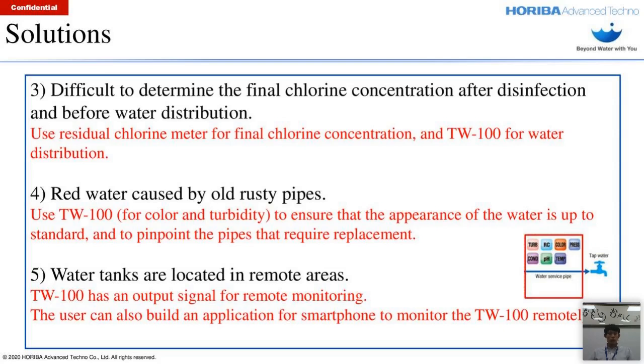For challenge number four, red water caused by old rusty pipes. The solution for this challenge is to use the TW100 series again to monitor the color and turbidity of the water. Measurement readings with high color and turbidity would mean that the water condition is not within permissible limit. So this would also allow us to determine which pipes are the cause of the red water.